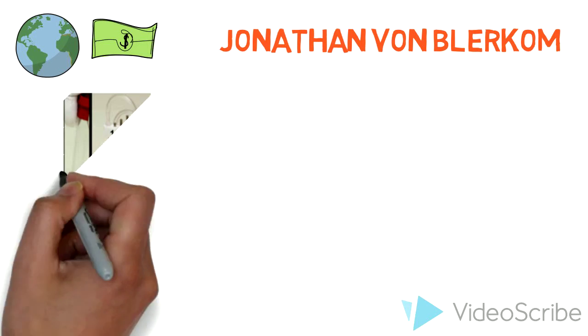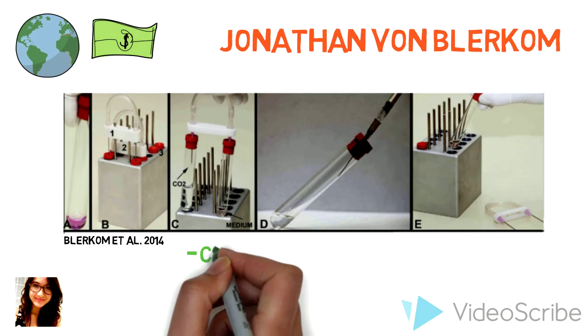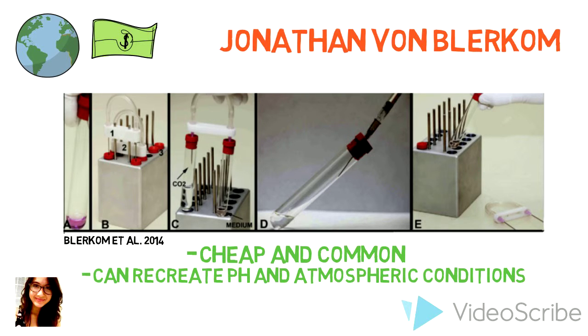This system works through an incubator system consisting of 2 sterilized glass tubes and a block of aluminum that heats the tubes to 37 degrees Celsius. In one of the tubes, citric acid and sodium bicarbonate mix with water to make CO2. These chemicals were chosen because of how cheap and common they are, and because they can mix to make the same stable pH in atmospheric conditions that medical-grade gases and microprocessor-controlled tissue culture incubators can.